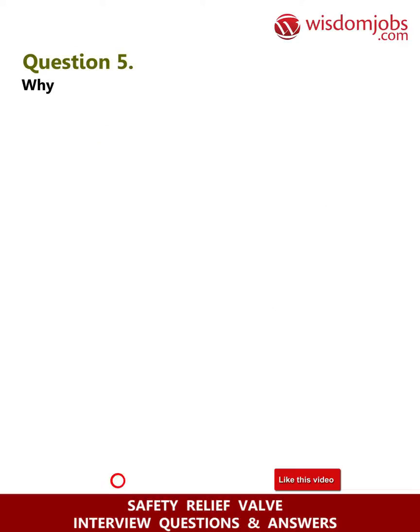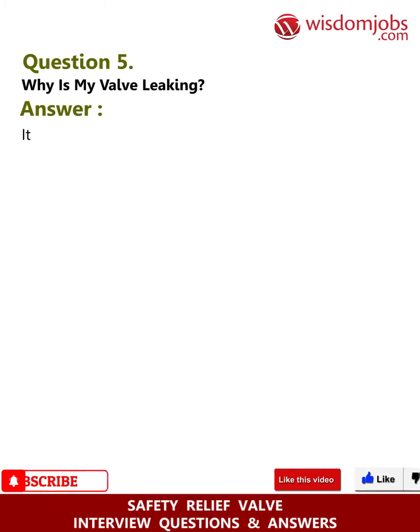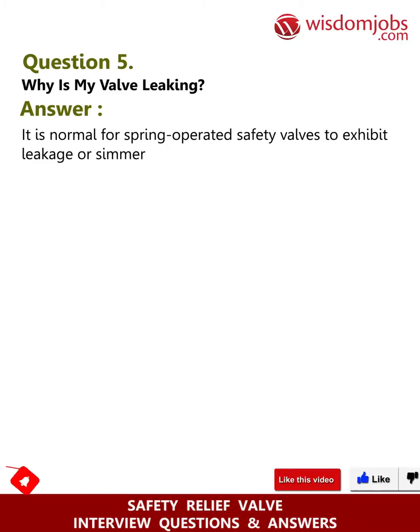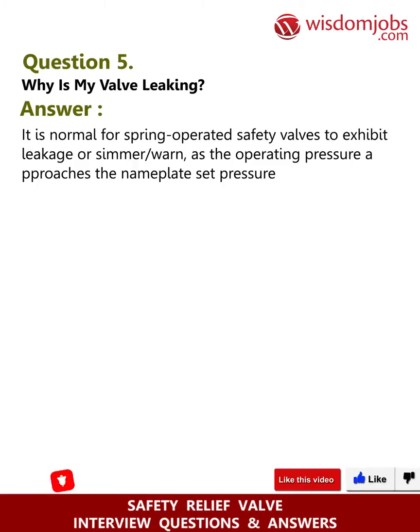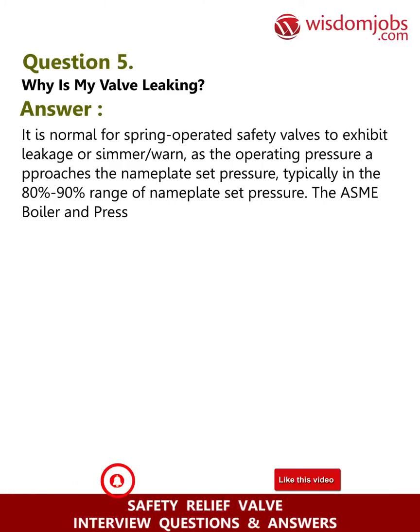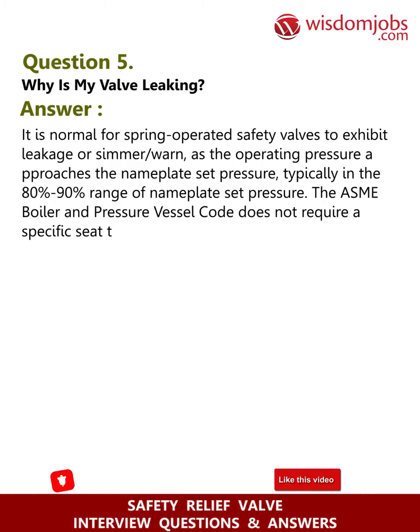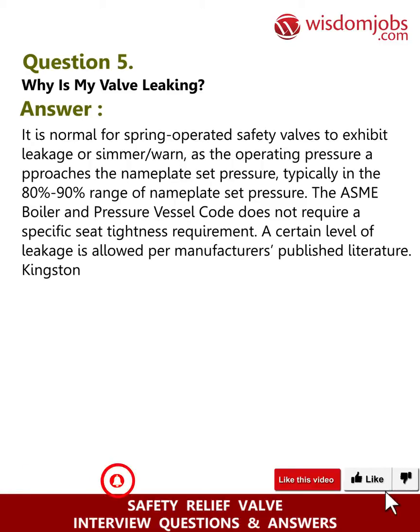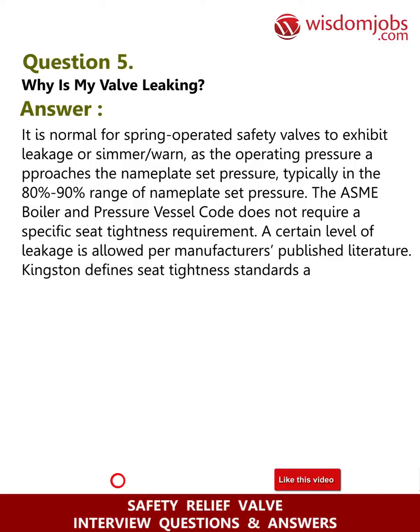Question 5: Why is my valve leaking? Answer: It is normal for spring-operated safety valves to exhibit leakage or simmer/warn as the operating pressure approaches the nameplate set pressure, typically in the 80 to 90 percent range of nameplate set pressure. The ASME Boiler and Pressure Vessel Code does not require a specific seat tightness requirement.